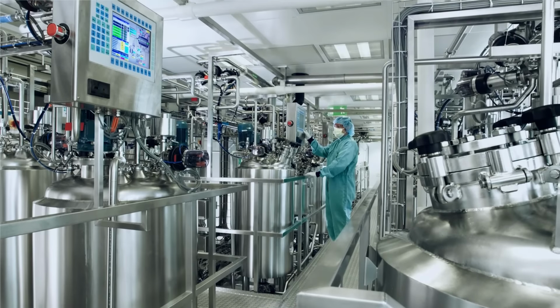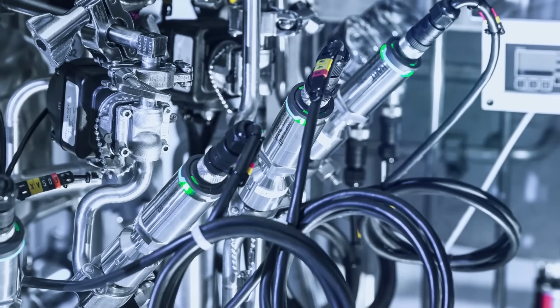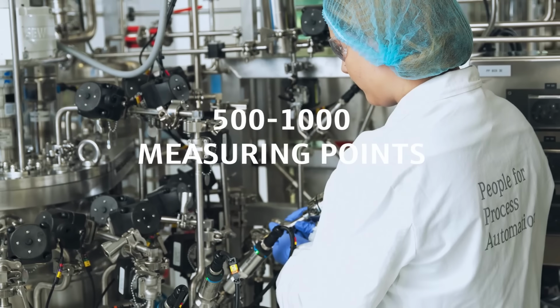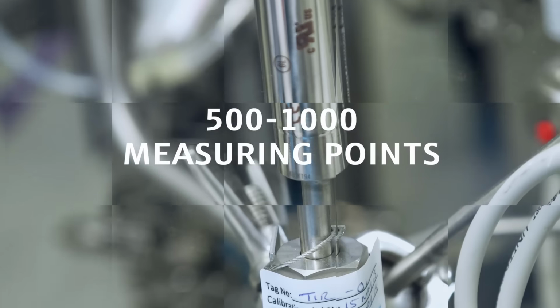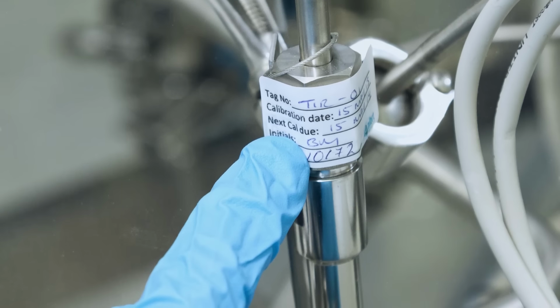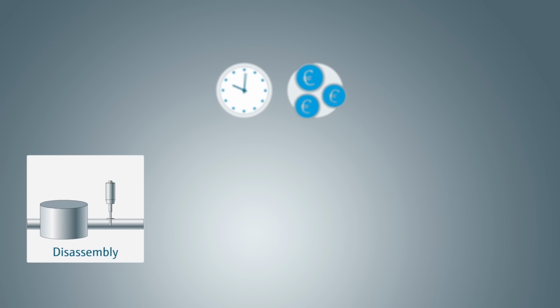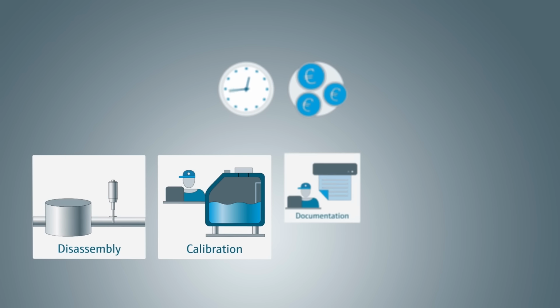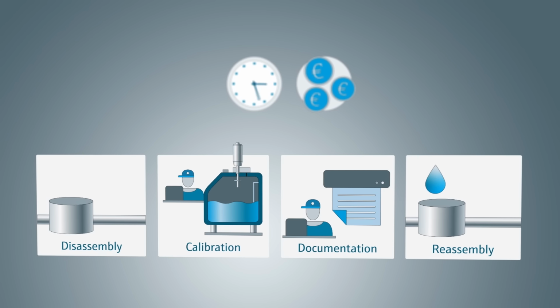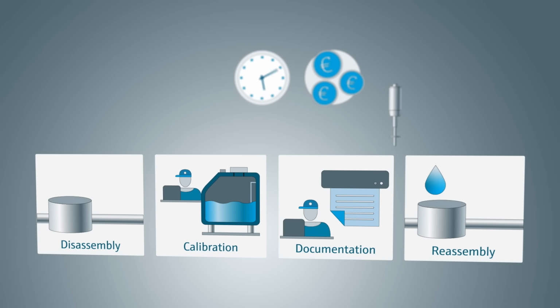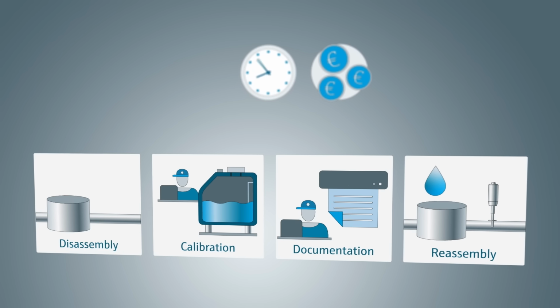A modern biotechnology production plant for manufacturing medicinal products typically contains between 500 and 1,000 temperature measuring points, which all need to be regularly calibrated. This is a time-consuming and expensive process and involves shutting down the production plant, as all temperature sensors in the plant need to be removed and reinstalled as part of calibration.